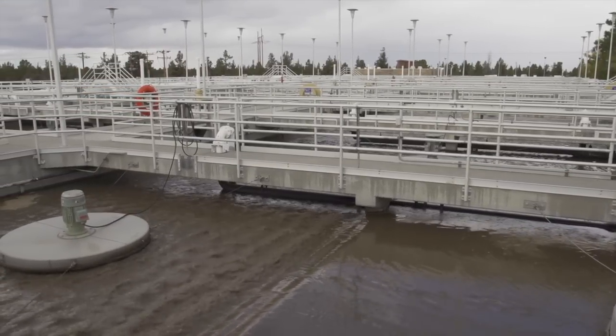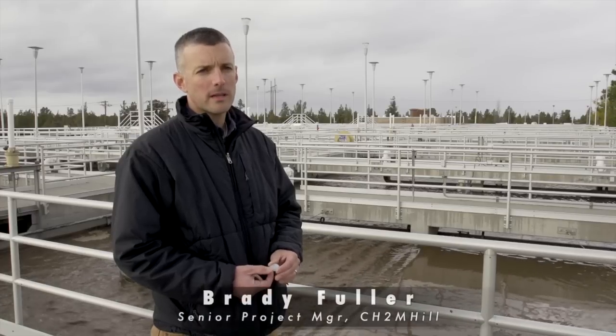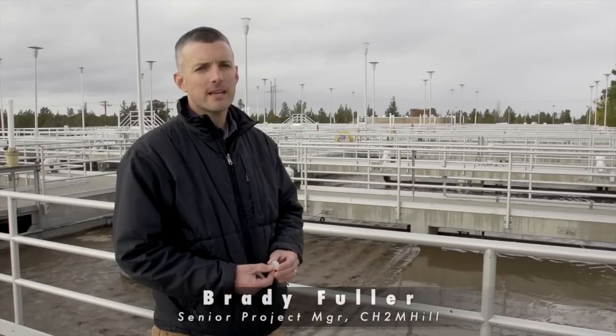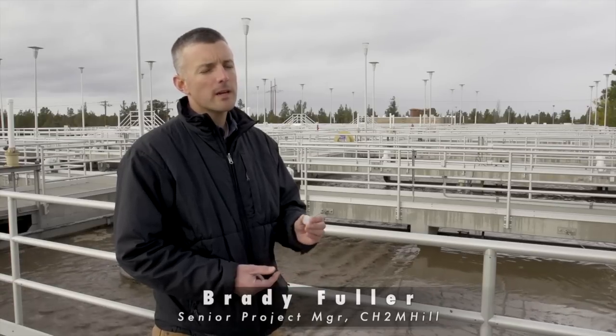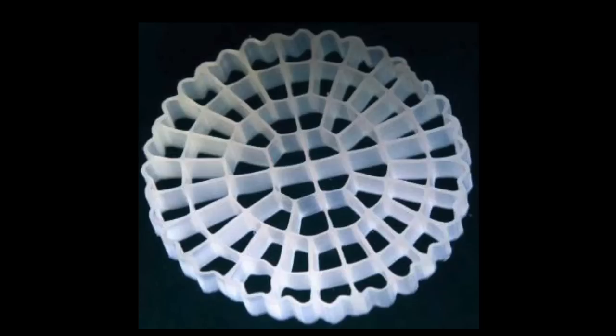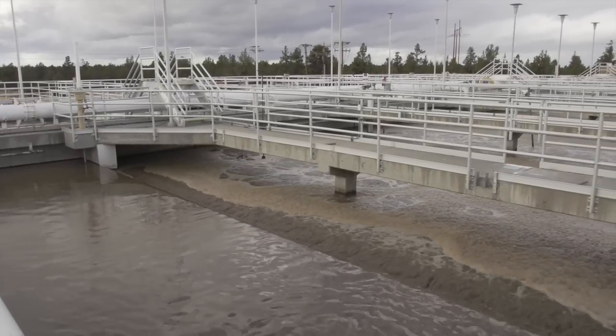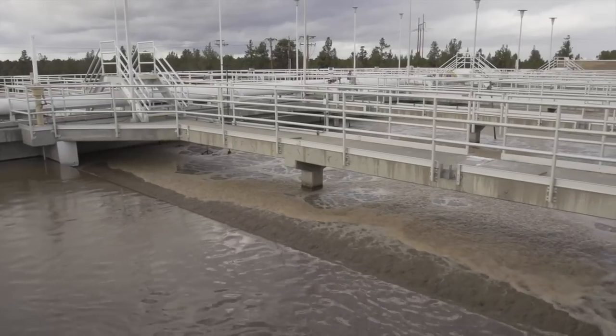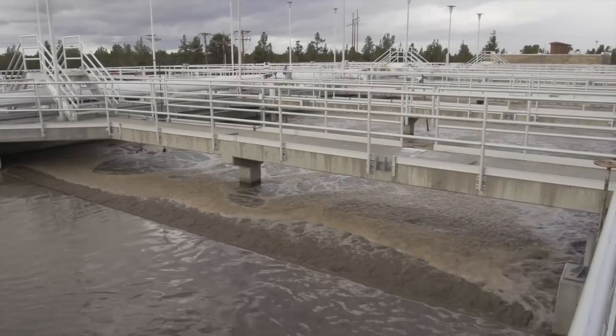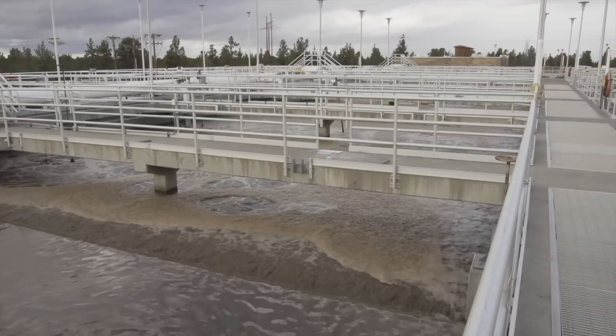How well can we use the existing tankage and facilities that we have? Our team helped the City through a selection process that selected IFAS technology, which is integrated fixed film activated sludge. Essentially, we're going to take many truckloads of these plastic media and put them into a new compartment within each of the existing aeration basins. A biofilm will grow on the media and that will provide a very high efficiency treatment process that will improve the efficiency of the basins. By adding the IFAS carrier media in the aeration basins, we're able to treat more in two aeration basins than the City is currently treating in three.